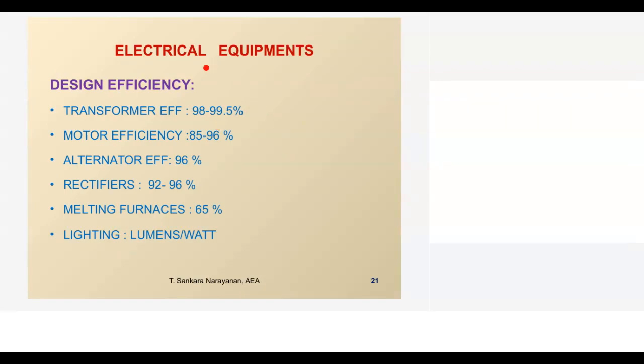So now when we talk of main electrical equipment, the transformer has been designed up to 99.5% efficiency. Then what do I have to do as an end user, or what should an auditor do, because my design efficiency is already 99.5? Similarly, if you consider a high tension motor, today I can go up to 97% efficiency. In the lower range, there can be an efficiency drop. All the generator alternators are 96% efficient by design itself. This has been there for a long time. It is not that they have only now increased the efficiency. For rectifiers, again the efficiency ranges between 92 and 96. All the electrical melting furnaces, if you do the heat balance, can have 65% efficiency.